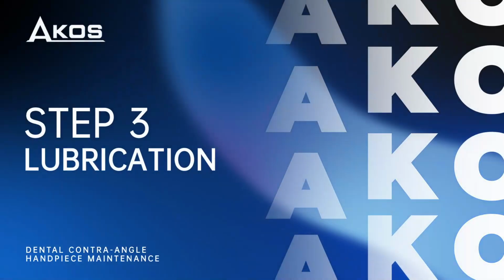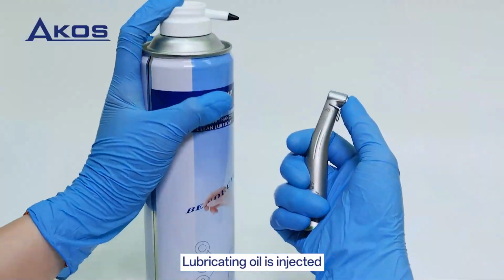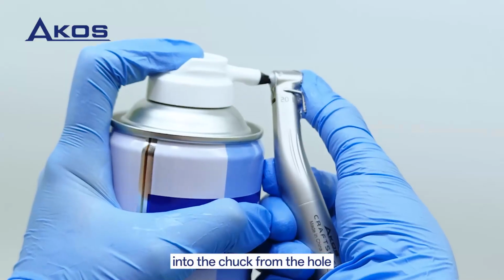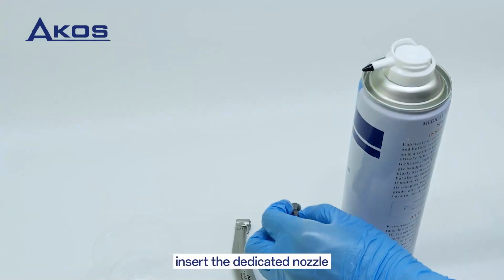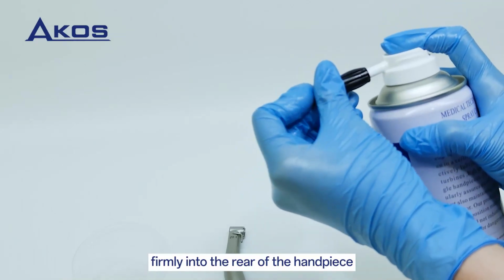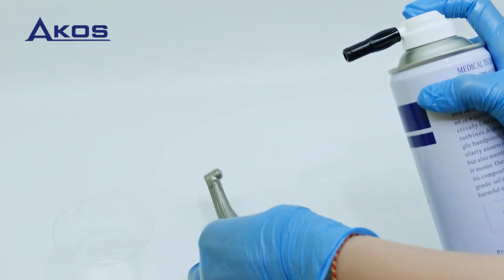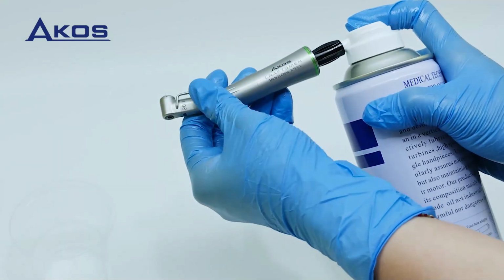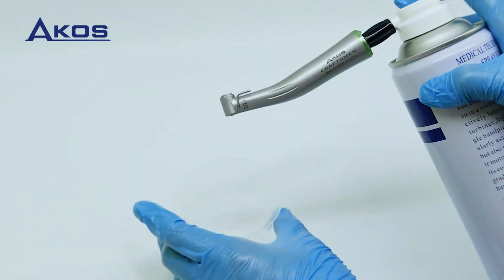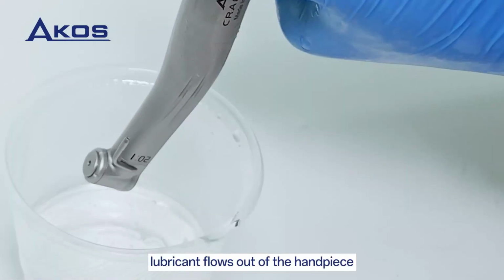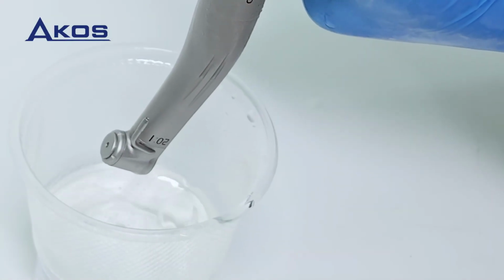Step 3. Lubrication. Lubricating oil is injected into the chuck from the hole. Insert the dedicated nozzle firmly into the rear of the handpiece. Continue until clean lubricant flows out of the handpiece.